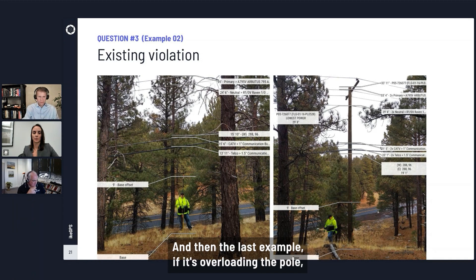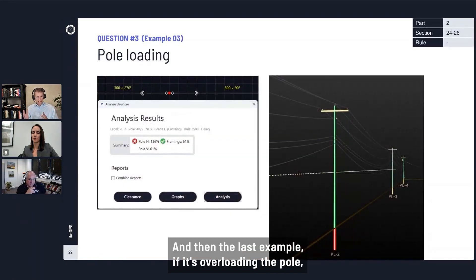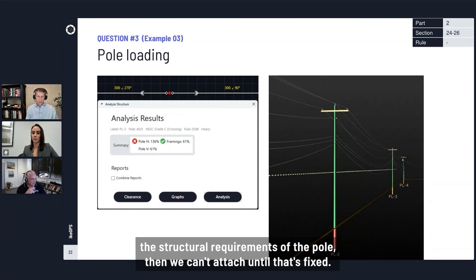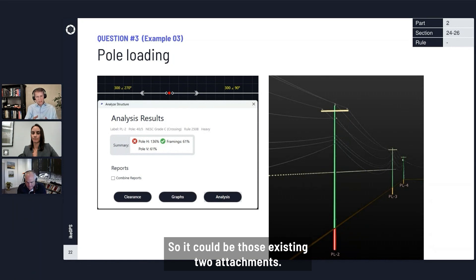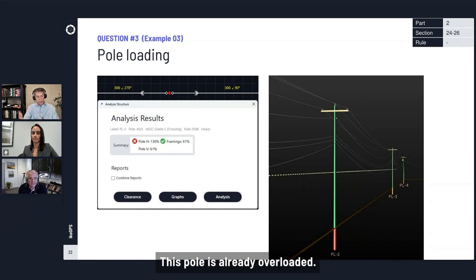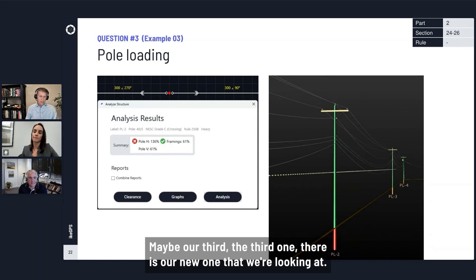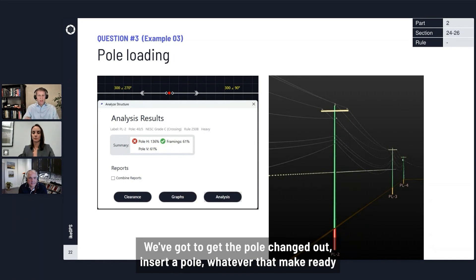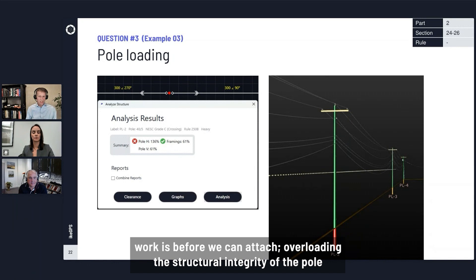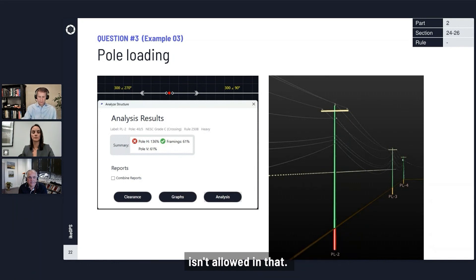If you go ahead with that attachment in a case like this, you may have to come back — transfer to a new pole if they change it out, or do some other make-ready work so those other violations can be fixed. We can go ahead and attach in cases where it's not endangering life or property. The last example: if the existing attachments are overloading the structural requirements of the pole, we cannot attach until that's fixed. If our new third attachment is what overloads the pole, we've got to get the pole changed out — whatever that make-ready work is — before we can attach.